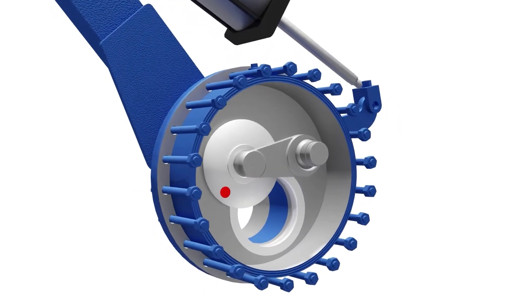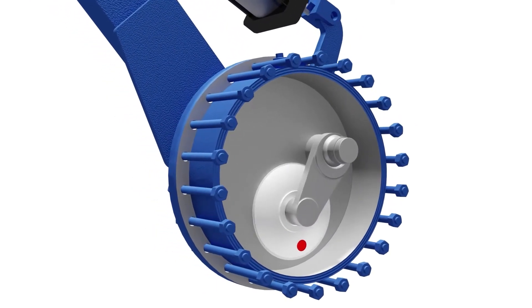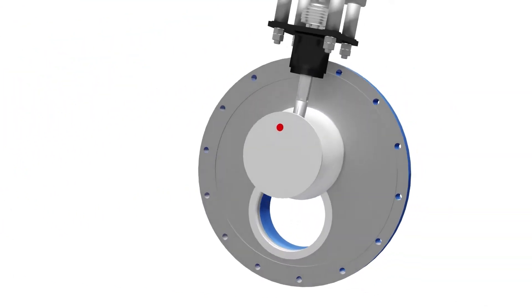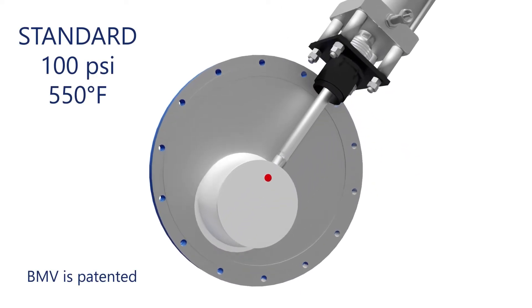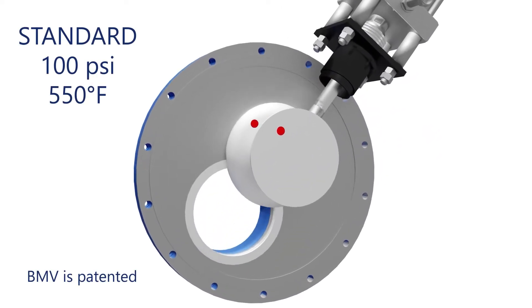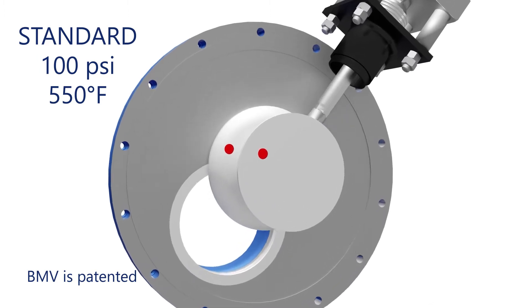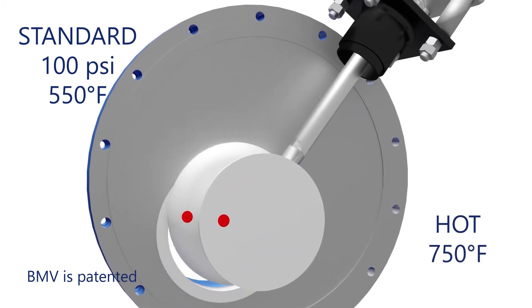The ProValve is for use in both slurries and dry solids where an ANSI class valve is needed. The Bulk Material Valve, or BMV, handles dry solids up to 100 psi and 550 degrees Fahrenheit in its standard design, and up to 750 degrees Fahrenheit in the hot design configuration.